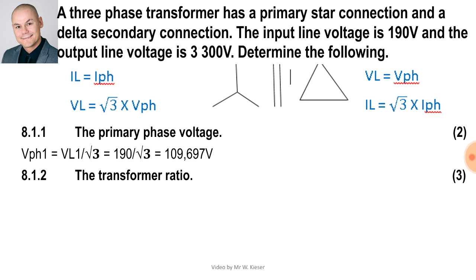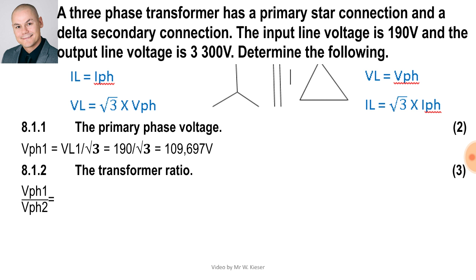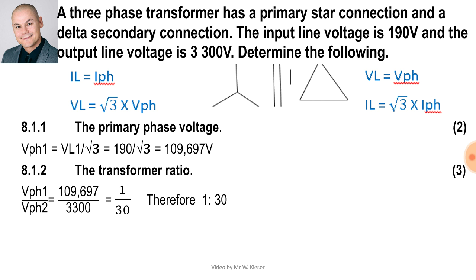To calculate the transformer ratio, when using the equation we use phase values, so it's V phase one over V phase two. V phase one is 109.697 volts. On the secondary side it's delta connected, so the line voltage and phase voltage are the same: 3300 volts. 109.697 is the smaller value — it goes into itself once and into 3300 thirty times. Therefore the ratio is 1 on the primary and 30 on the secondary.